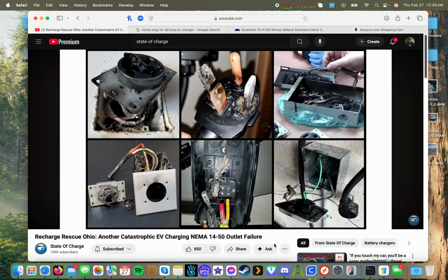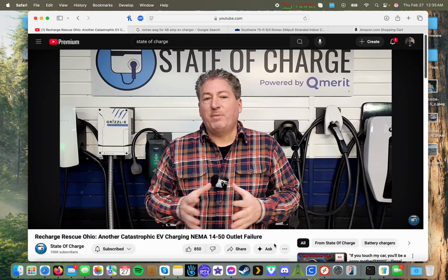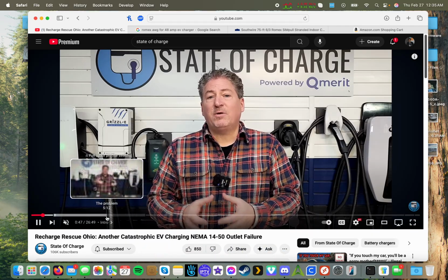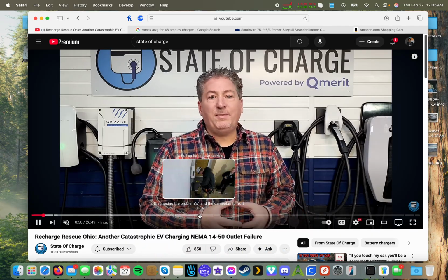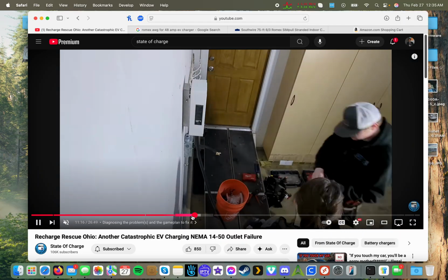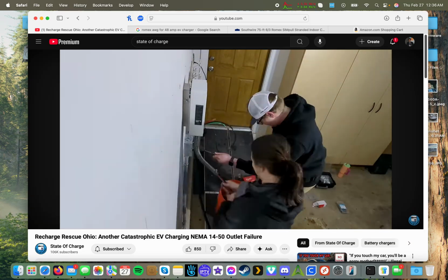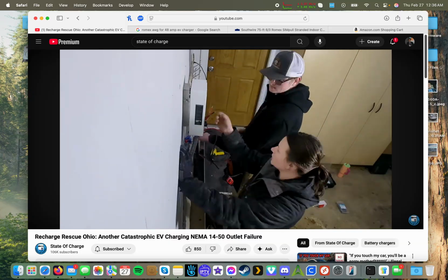This is his latest video where he went to help someone with a burned outlet, and they installed a new hardwired 48-amp charger in the garage. But the part that got me was that they derated it to 40 amp and replaced the 60 amp breaker with a 50 amp breaker. And I'm like, why would they do that? In the video, he doesn't tell you if the wire is 6 gauge or 8 gauge. He just says that was what they did because I guess that was what they needed to do.